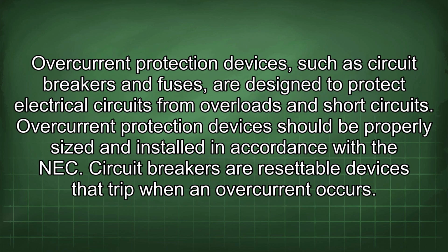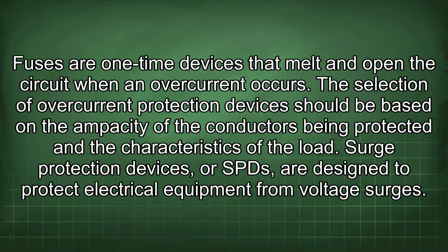Overcurrent protection devices, such as circuit breakers and fuses, are designed to protect electrical circuits from overloads and short circuits. Overcurrent protection devices should be properly sized and installed in accordance with the NEC. Circuit breakers are resettable devices that trip when an overcurrent occurs. Fuses are one-time devices that melt and open the circuit when an overcurrent occurs. The selection of overcurrent protection devices should be based on the ampacity of the conductors being protected and the characteristics of the load.